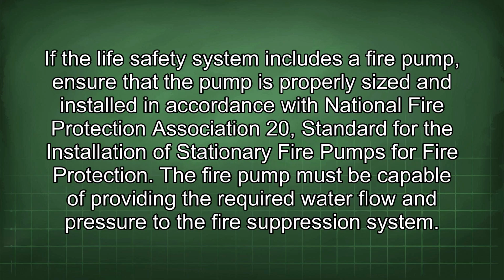If the life safety system includes a fire pump, ensure that the pump is properly sized and installed in accordance with National Fire Protection Association 20, the standard for the installation of stationary fire pumps for fire protection. The fire pump must be capable of providing the required water flow and pressure to the fire suppression system.